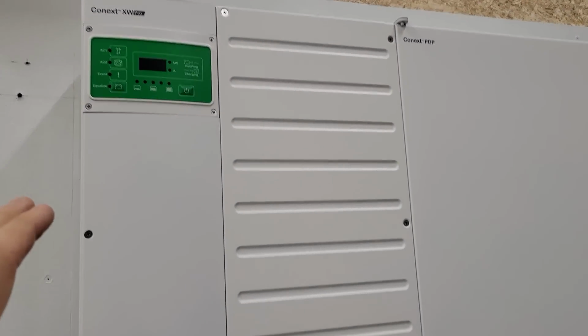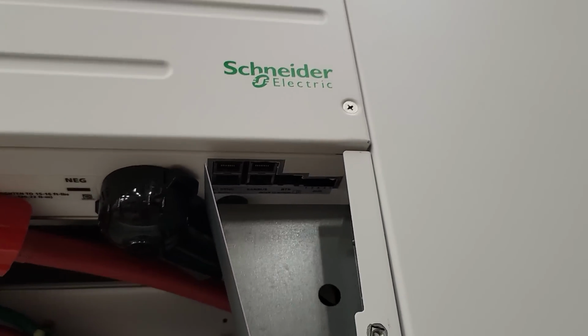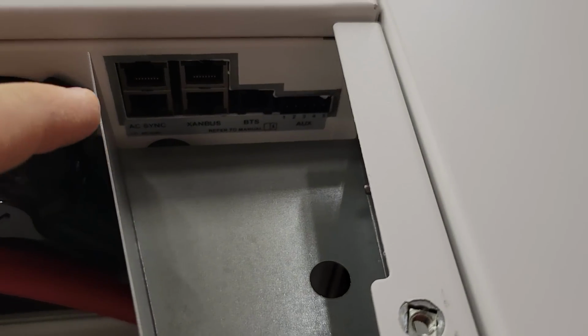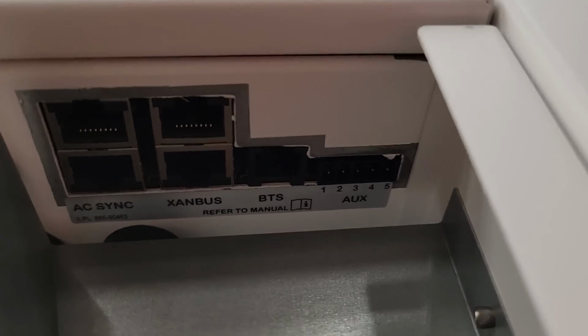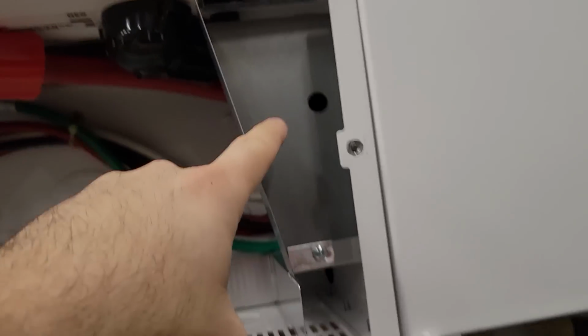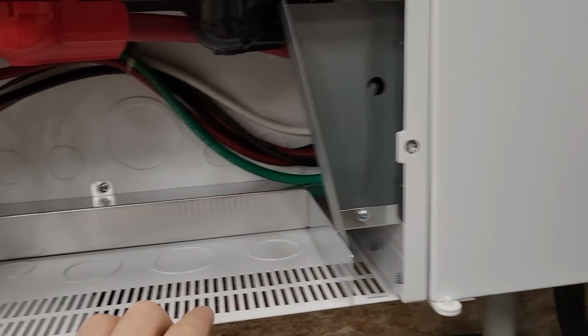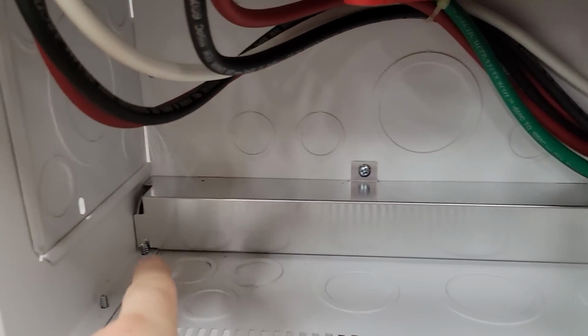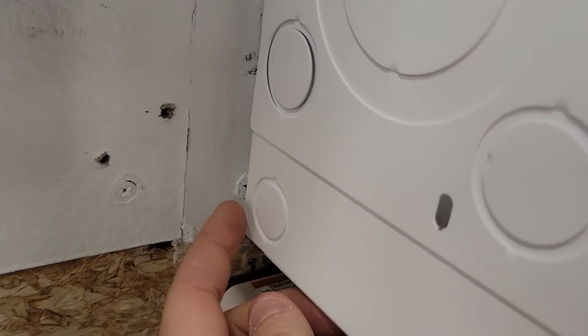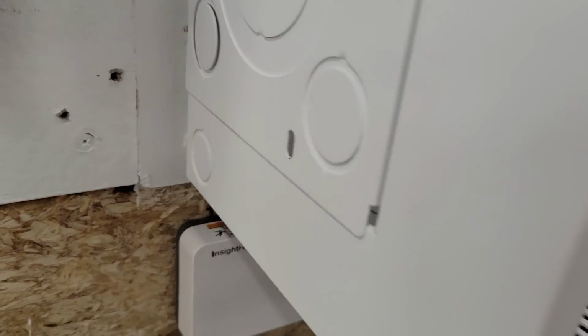I've turned off all the power for the inverter. Underneath the inverter, this is where the communication ports line up. And we have two that are Xanbus right there in the middle. So what I'm gonna do is run an Ethernet cable down. I'll take off this back tray and we'll pop out this 3/4 inch knockout and put in a bushing. So let's go ahead and do that now.